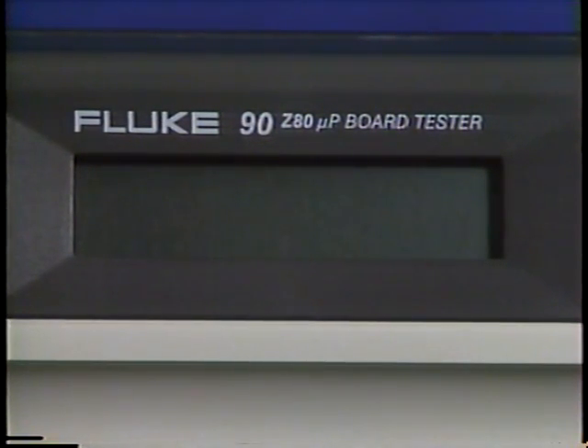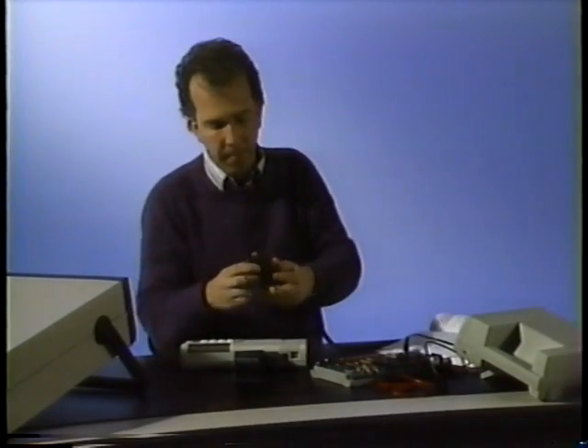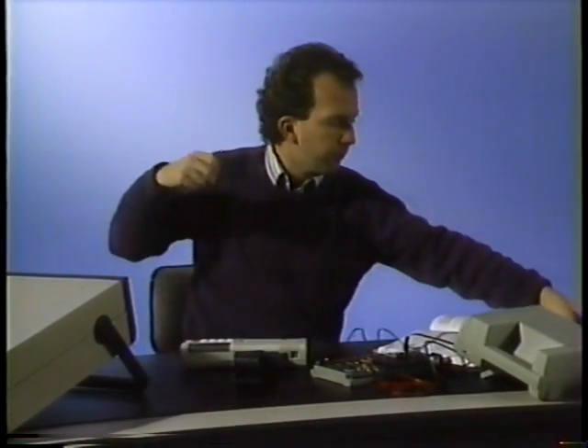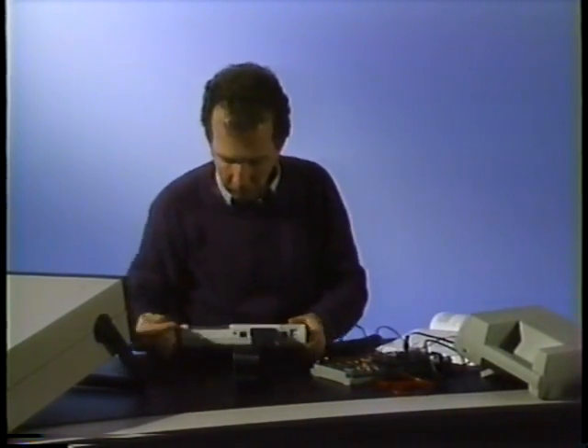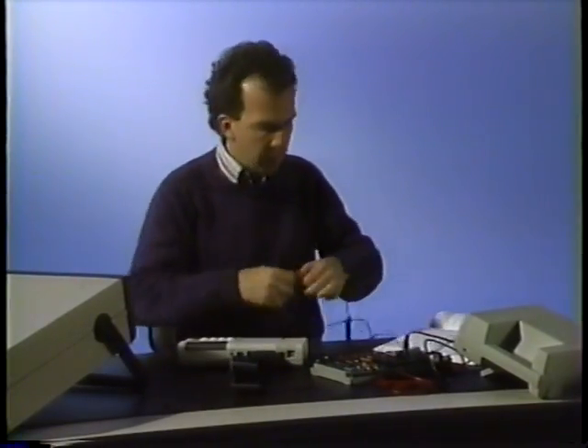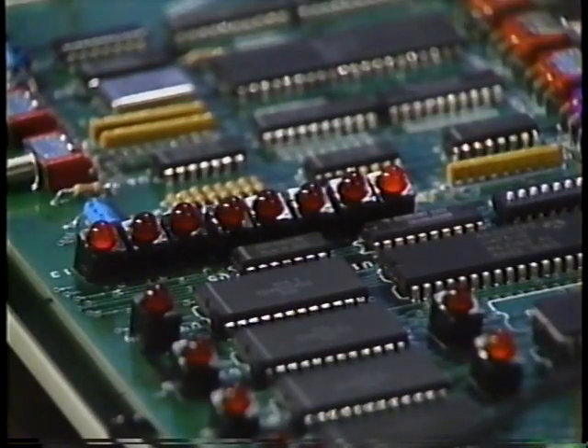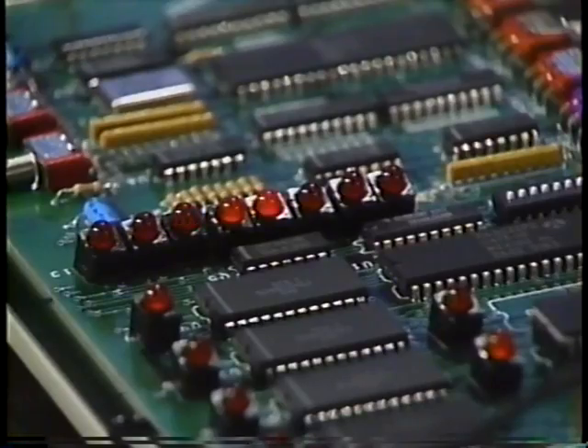Each Fluke 90 supports one and only one type of microprocessor, as indicated on the front of the instrument. That's the first thing to remember. Second, the UUT must have an operational plus 5-volt power supply, or you must connect an external power pack to power the Fluke 90, independent of the unit under test. Third, unless an external power supply is used, the UUT power supply must be able to supply current to the Fluke 90. The Fluke 90 adds a maximum of 150 milliamps of load to the UUT power supply.